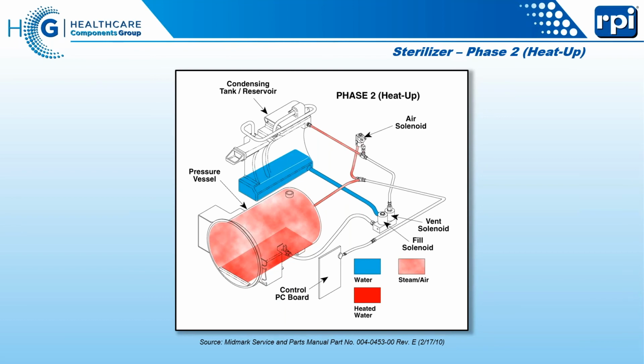You should not be putting hot water in there, and you should not be putting water in until the chamber is below the boiling point of water so that it's not immediately flashing into steam. That takes about 10 to 15 minutes. So that's the logic behind it. And you can tell them, if they start the machine and the first thing they hear out of this thing is gurgling, that's bad. That's that water hitting the heated bottom, turning into steam, and gurgling back through the fill valve, screwing everything up. Sir?